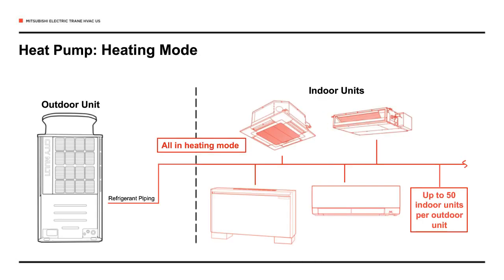So let's break down those systems that I talked about. At its most basic, a VRF system consists of an outdoor unit and a network of indoor units connected by refrigerant lines and governed by controls and sensors. VRF heat pumps are effective when all of the building zones can be in the same mode at the same time, either heating or cooling. The outdoor unit contains a compressor, condensing coil, reversing valve, and condenser fan. Each outdoor unit may be connected to multiple indoor units, and individual outdoor units may be combined to increase tonnage.